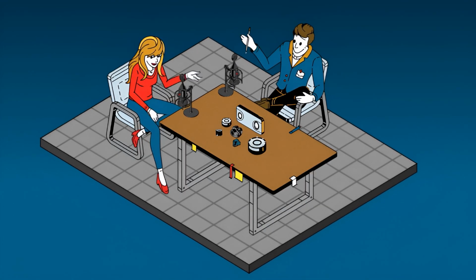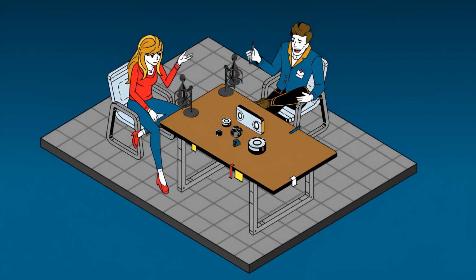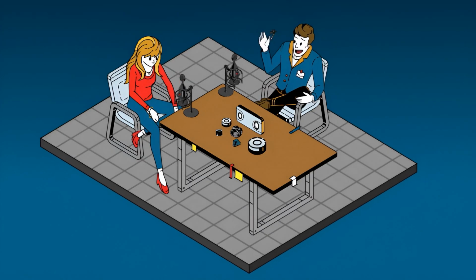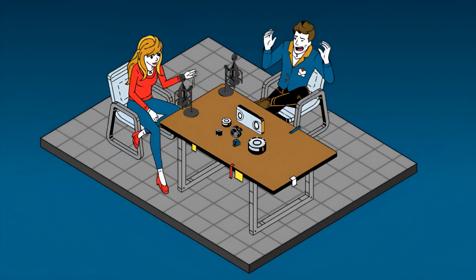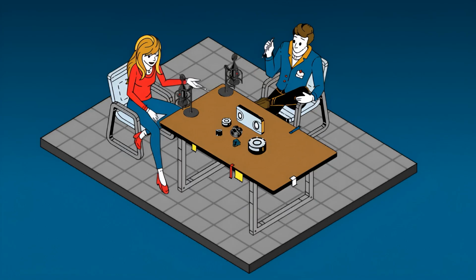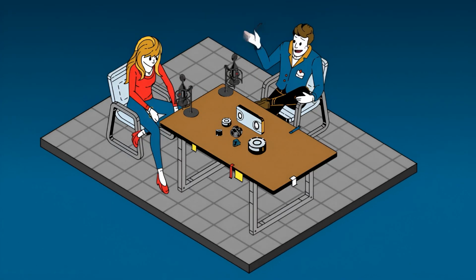So how does that conversion actually happen? Most high-precision load cells use strain gauges—tiny, microscopic sensors bonded onto a specially designed metal part inside the load cell called the flexure. When you apply force, push or pull, that metal flexure bends or deforms just a tiny bit, sometimes only a few thousandths of an inch.